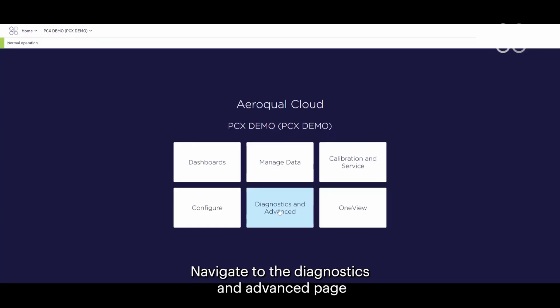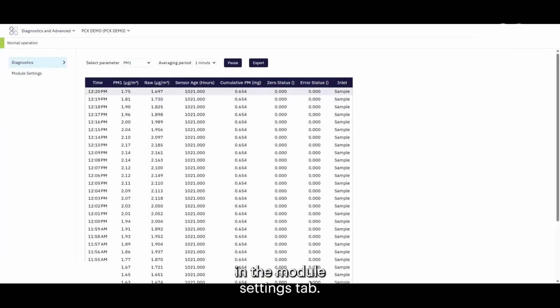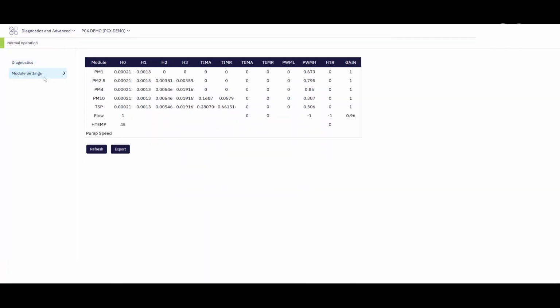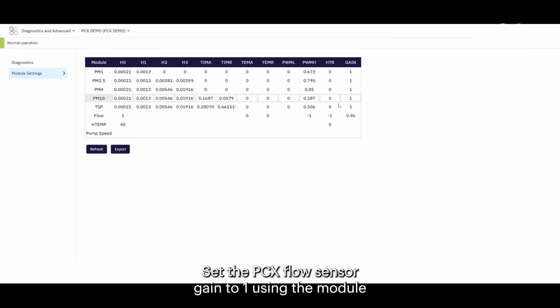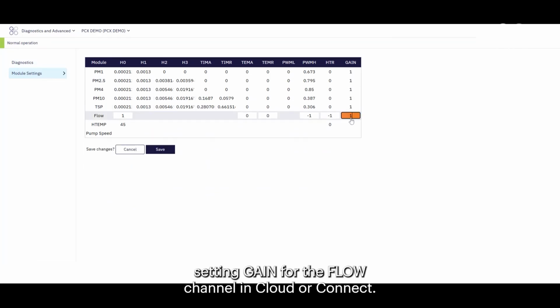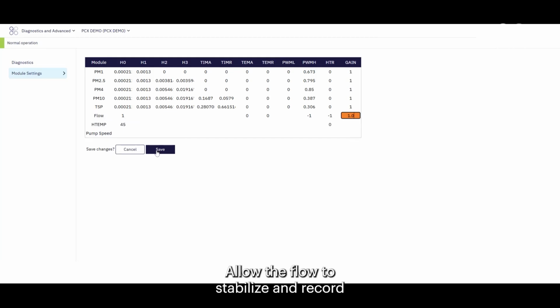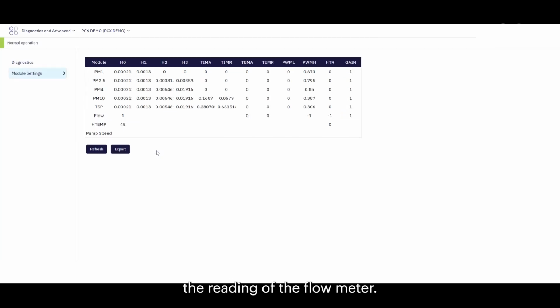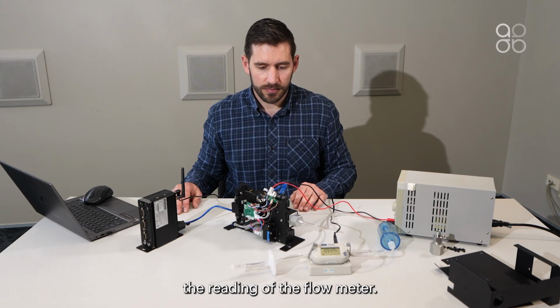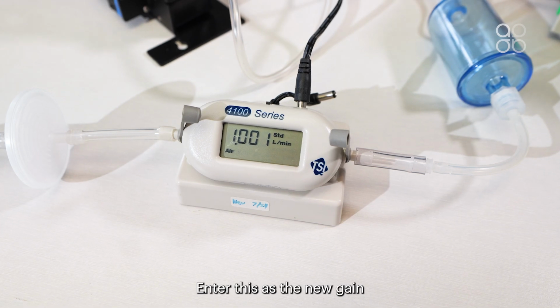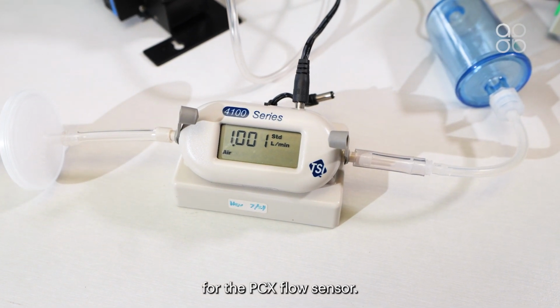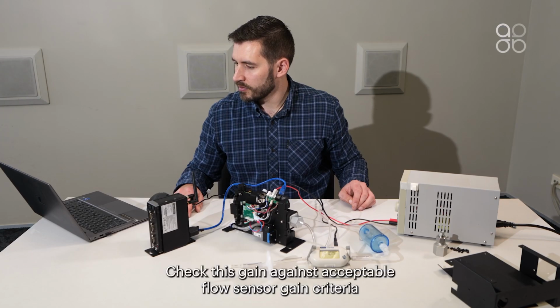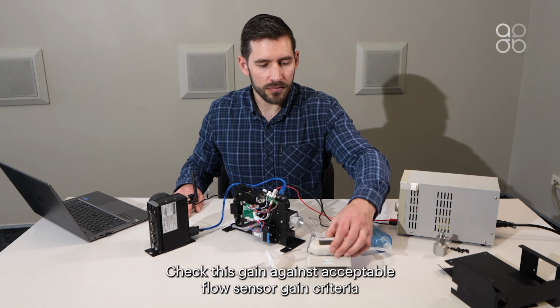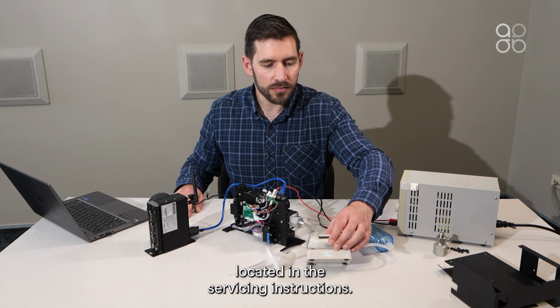Navigate to the Diagnostics and Advanced page and the Module Settings tab. Set the PCX's flow sensor gain to 1 using the module setting gain for the flow channel in Cloud or Connect. Allow the flow to stabilize and record the reading of the flow meter. Enter this as the new gain for the PCX's flow sensor. Check this gain against the acceptable flow sensor gain criteria located in the servicing instructions.